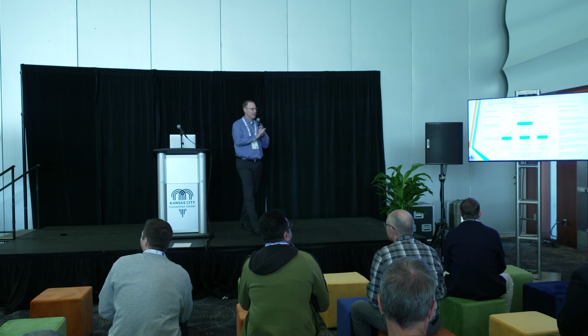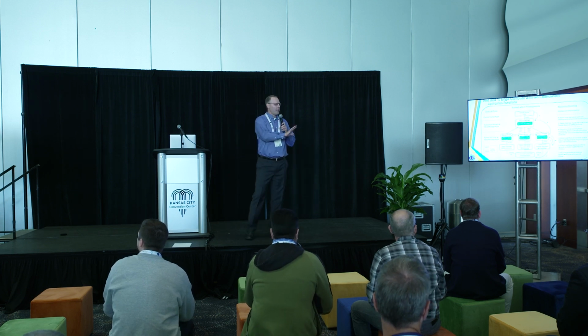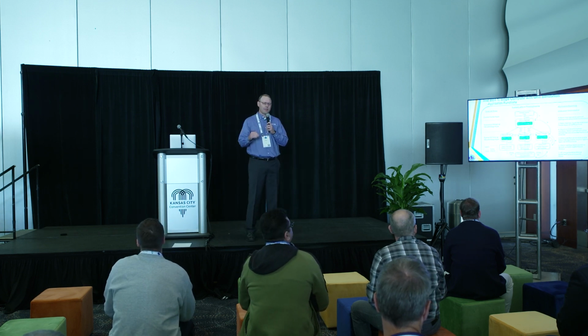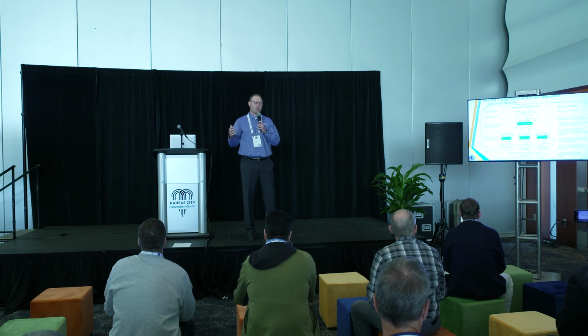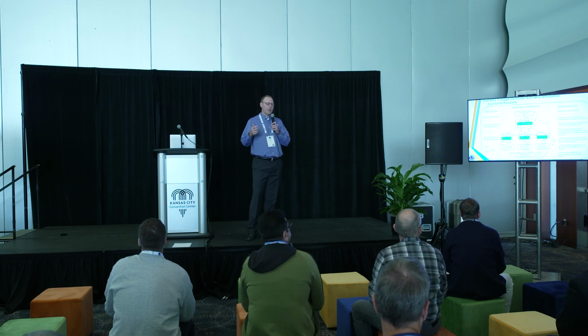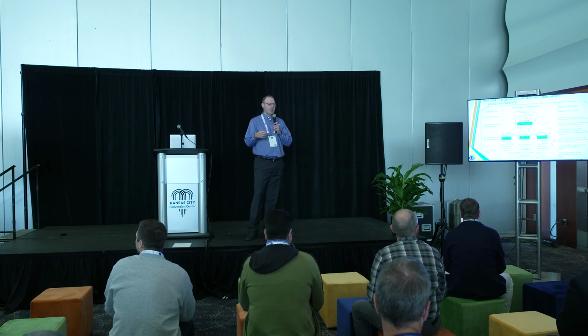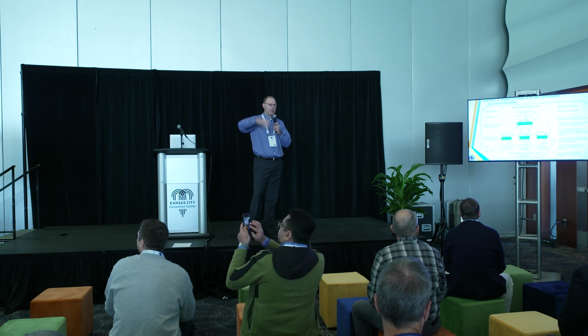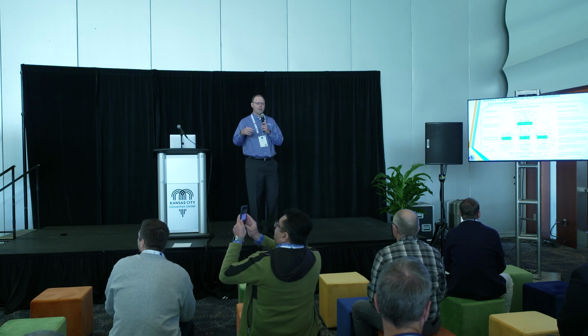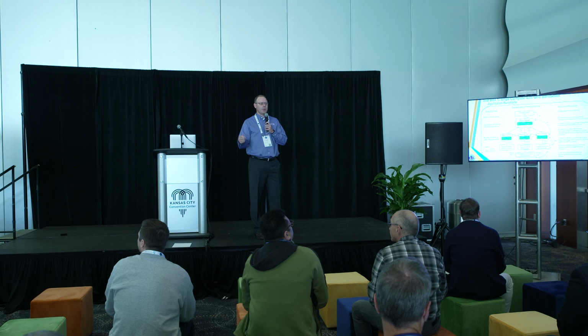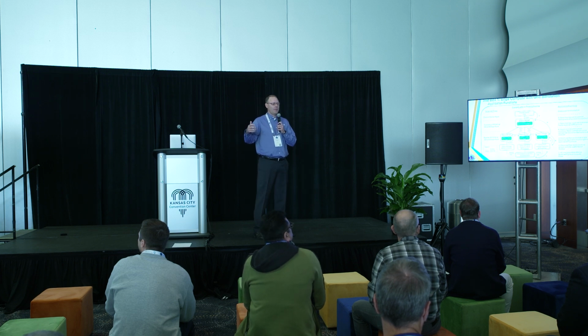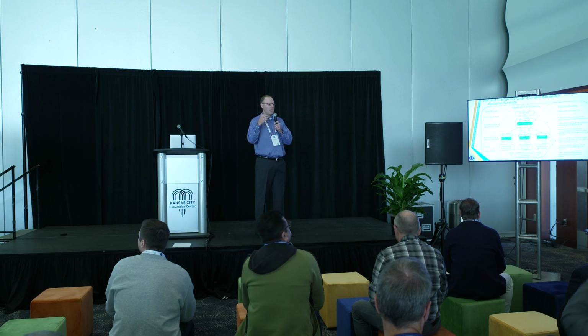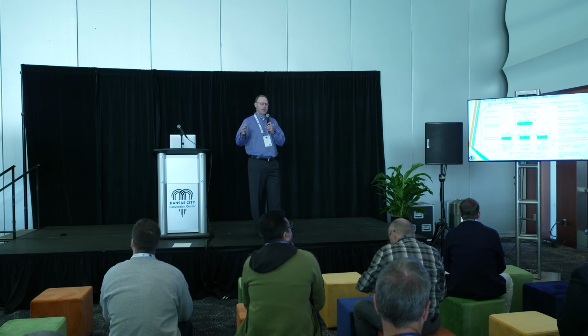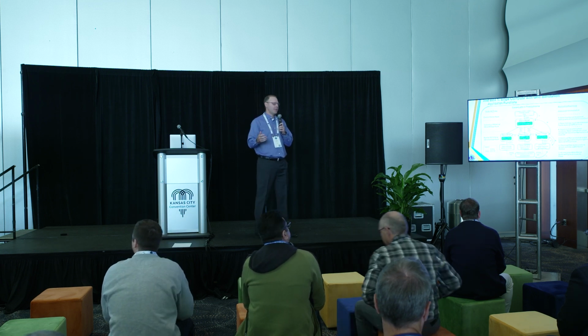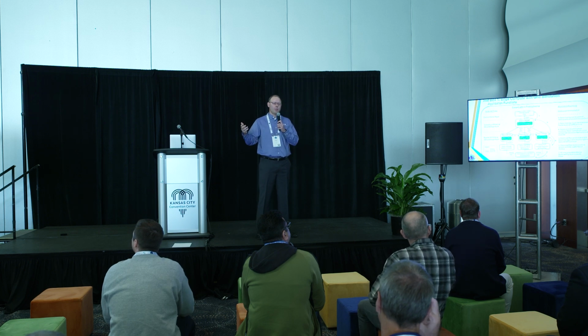I don't want to go through all the details here, but the main point is it's a multi-level control system, and with a very strong, secure communication backbone, we can put applications at the edge that communicate not only traditionally north-south, with translators from Modbus for a DER system or DNP3 for a capacitor bank or regulator controller, but also east-west between those devices using publish-subscribe protocols that have mutual transport layer security between them.